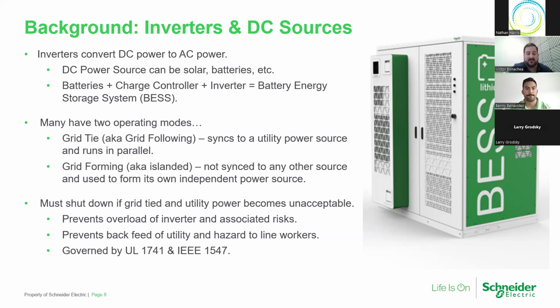Your inverter, your BESS, is going to try to feed that entire load, which is going to overload your inverter and your BESS, causing damage to it, probably causing breakers to trip or nuisance shutdowns. So you want to avoid that as well. That raises the question: if I have to shut down the inverter when I'm operating in grid tie mode, which I want to do most of the time for energy cost optimization, then how can we use it for backup power as well? That's what this whole presentation leads into.